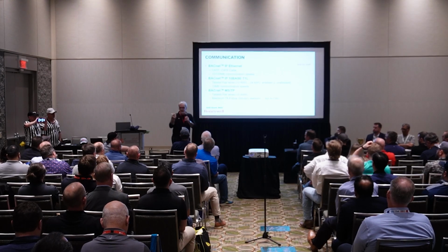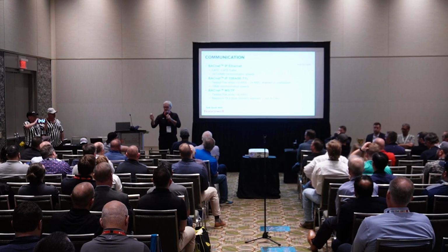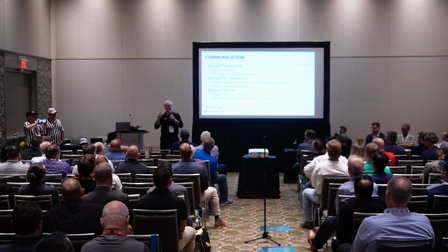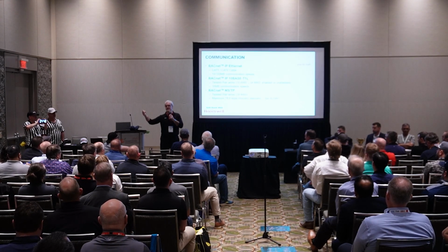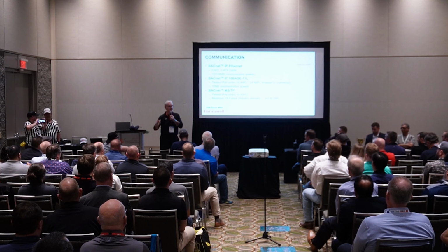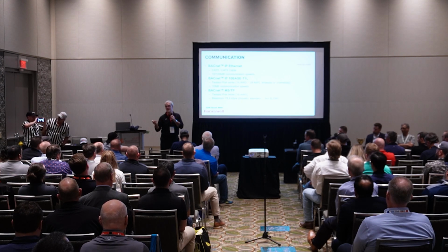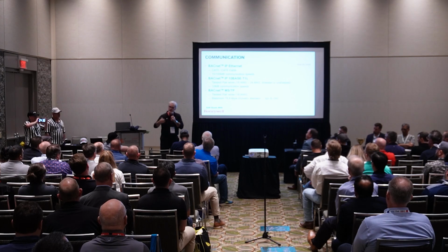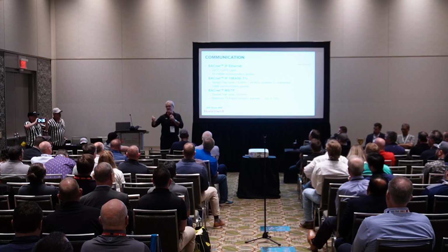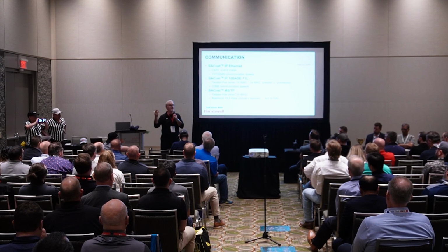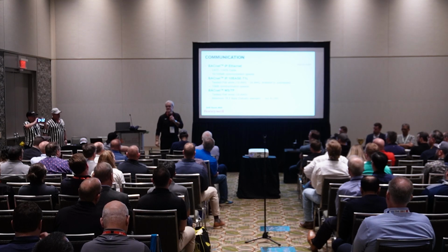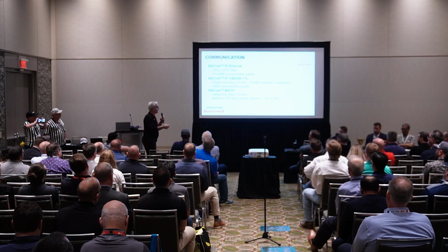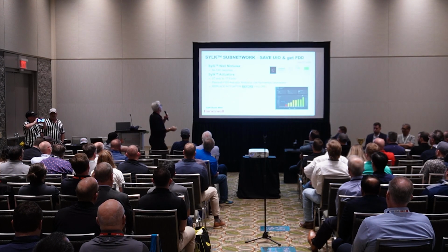So what is it? It's BACnet IP over twisted pair wires. I can go up to 1 kilometer between devices. It's an IEEE 802.3 standard, so it's not something we created, it's something we went out and found. I think MSTP is going to go away. If I can do installation costs the same as MSTP and provide IP controllers, why would I put in a slow system? There you go. So that's available on it.